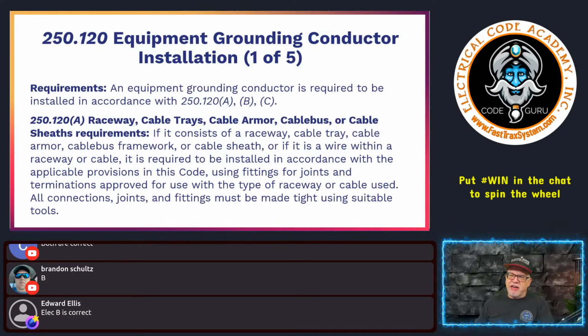All right, equipment grounding conductor installation. An equipment grounding conductor is required to be installed in accordance with 250.120(A), (B), and (C). Okay, so 250.120(A) says raceways, cable trays, cable armor, cable bus, or cable sheath requirements. If it consists of a raceway, cable tray, cable armor, cable bus framework, or cable sheath, or if it is wire within a raceway or cable, it is required to be installed in accordance with the applicable provisions of this code, using fittings for joints and terminations approved for use with the type of raceway and cable used. All connections, joints, and fittings must be made tight using suitable tools.